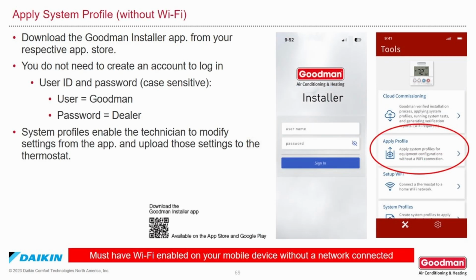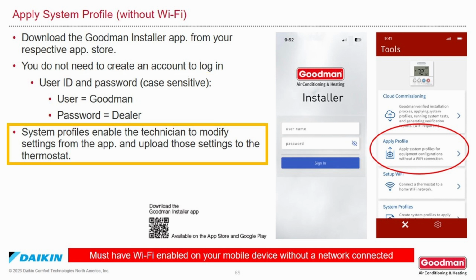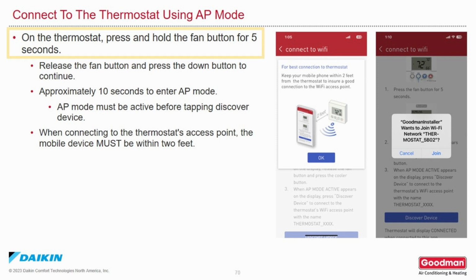Apply system profile without Wi-Fi. Download the Goodman Installer app from your respective app store. You do not need to create an account to log in. The default user ID and password, which are case sensitive, are user Goodman with an uppercase G, password dealer with an uppercase D. System profiles make it so the technician can modify settings from the app and then upload those settings to the thermostat. On the thermostat, press and hold the fan button for 5 seconds.